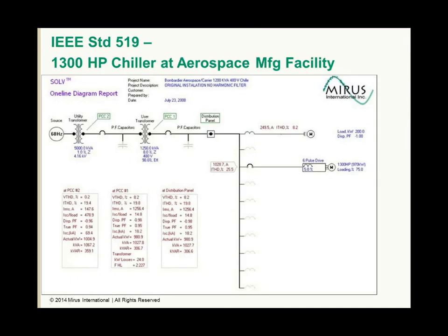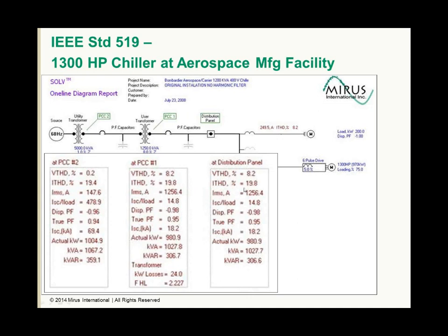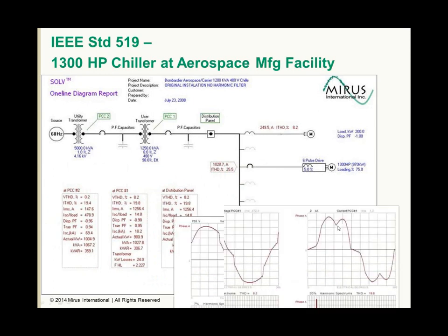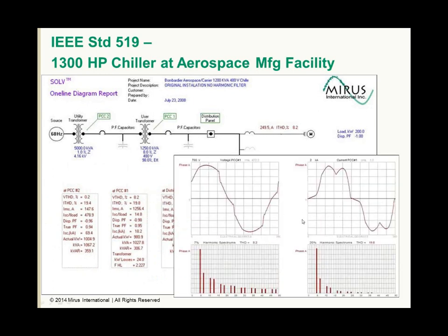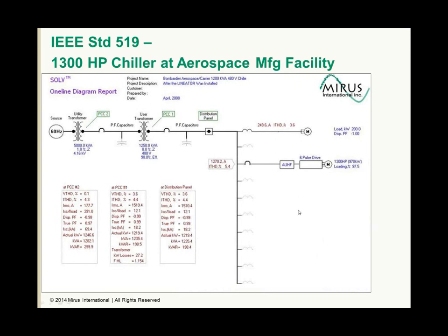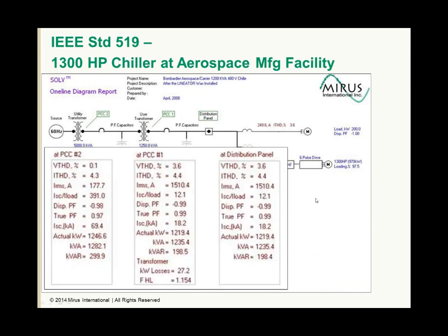Computer simulation was used to demonstrate why the 5% reactor was not an effective solution. We can see the current distortion and voltage distortion at the distribution panel and at the transformer, not meeting IEEE 519, resulting in distortion of the voltage, flat topping of the voltage waveform, which was restricting the chiller's operation. By replacing the 5% reactor with a Lineator AHF passive filter, harmonic distortion in the form of flat topping could be reduced and allowed the chiller to reach its full capacity.